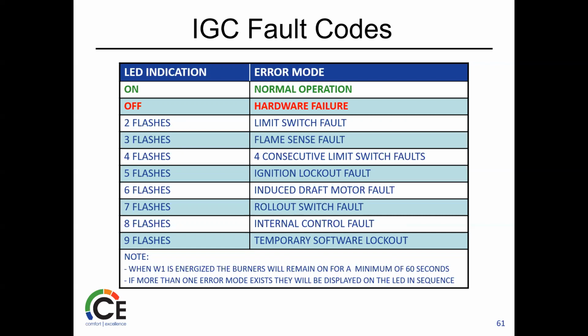And then again, there's those lockouts. If the limits went 4 times, you know, if it restarted and kept going out, that's when some of that changes. You're going to get a lockout. Maybe you get a 6, that's your induced draft. And then, so basically no light, or 8 and 9, a potential board failure. But again, you know, do your due diligence. If it's off, make sure it's powered first before you say, hey, I need a new board.